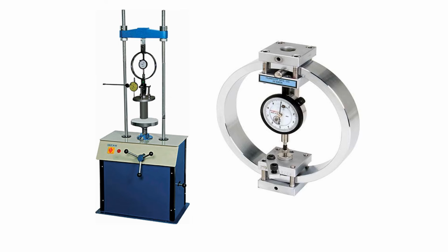Here we have this micrometer fitted inside the ring. At both ends of the ring we have the loading bosses, and in some proving rings we have strain gauges. Using 4 different strain gauges we can also make accurate measurements using the proving ring.